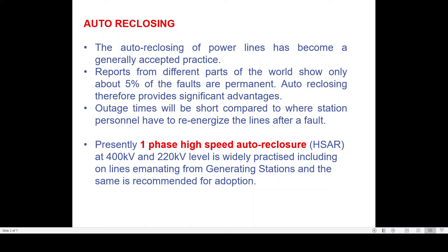Autoreclosing provides a significant advantage, as autoreclosing time is very short compared to energizing the line after every fault manually. Presently, for any transmission voltages above 220 kV or including 220 kV — that means 220 kV, 400 kV, 765 kV and more — the generally accepted practice is the single phase high speed autoreclosure.